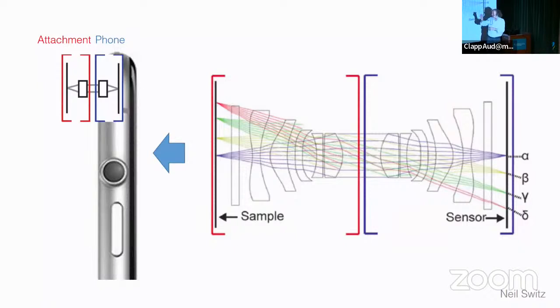In fact, for the aficionados, this is a non-telecentric imaging system, which means your magnification depends on your focal position. And the resolution you could obtain because of the lens numerical aperture is actually higher than the sensor, so we're actually pixel limited in terms of information collection. There's more information coming in the lens. So as the pixel densities get smaller and smaller, this sort of configuration will continue to gather more information.